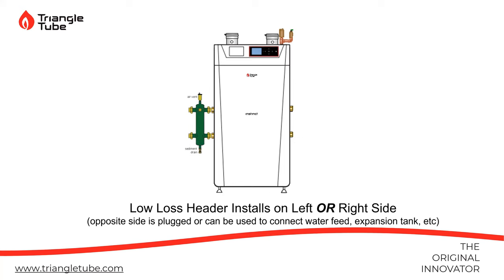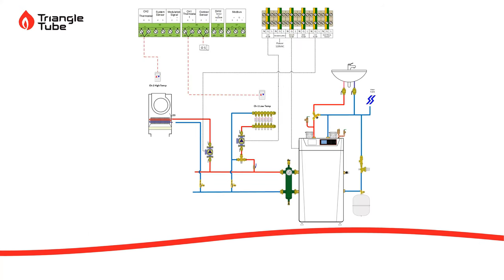That's showing the low loss header, other side. The domestic connections will come up right off the top. We have plenty of room back there if you want to use one of the Caleffi crossover mixing valves, which we highly recommend. I have one on the boiler right here that I'll show you on one of the wall hungs. Also, you will have your air vent and relief valve piped off the top right here. This comes in the box as a little accessory box with the boiler. And then your vent terminations come off the top as well.